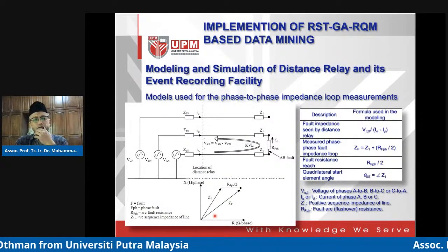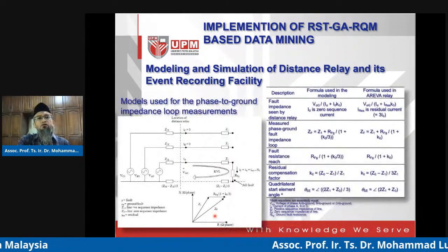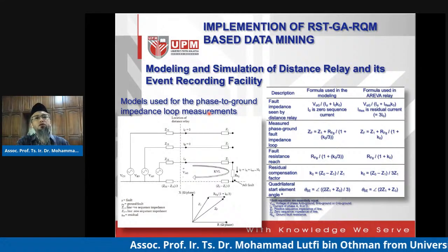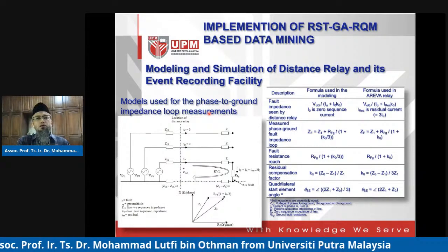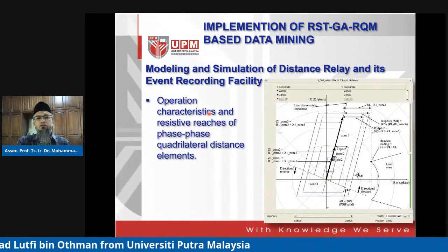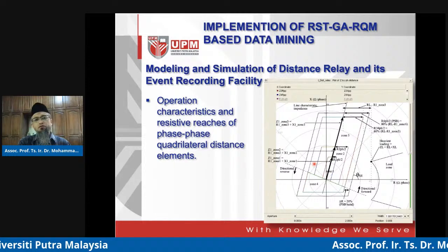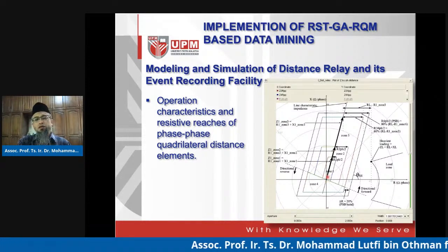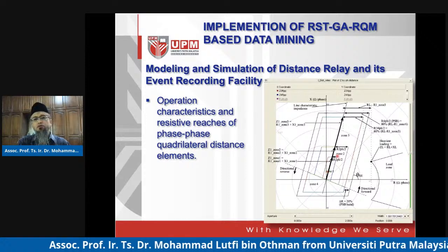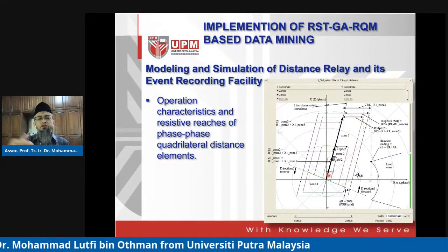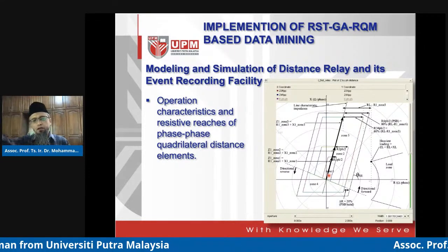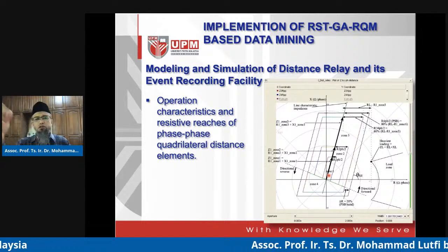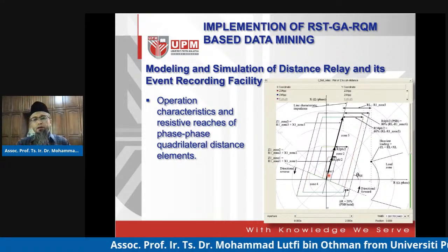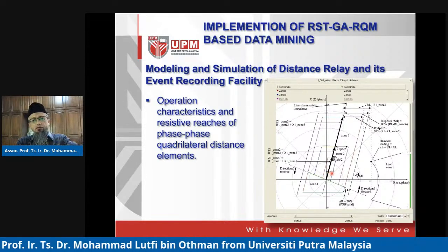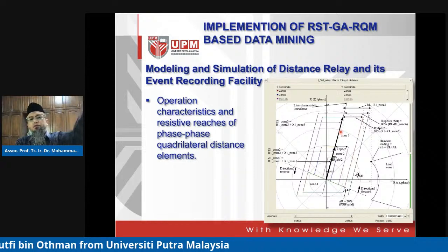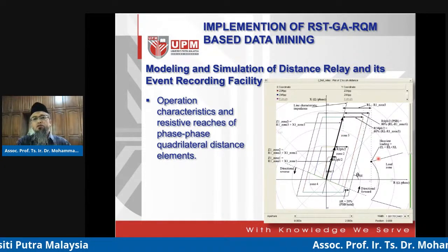So this is the basic operation characteristic of phase-to-phase impedance measurement of the distance relay, and the basic fundamentals of phase-to-ground measurement of impedance for faults involving ground. And this is the operation characteristic of the phase-to-phase quadrilateral distance element. As you might know how a distance relay operates, we have zone 1, zone 2, zone 3. It depends on how much coverage you are dealing with as far as the transmission line that this distance relay is protecting against the fault. Zone 1 is a much closer location of fault. Zone 2 is further. Zone 3 is further away, beyond the next substation possibly, right?